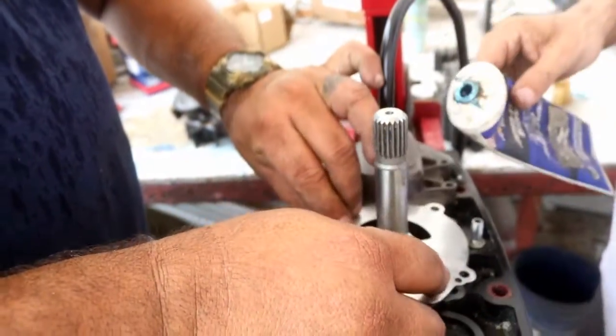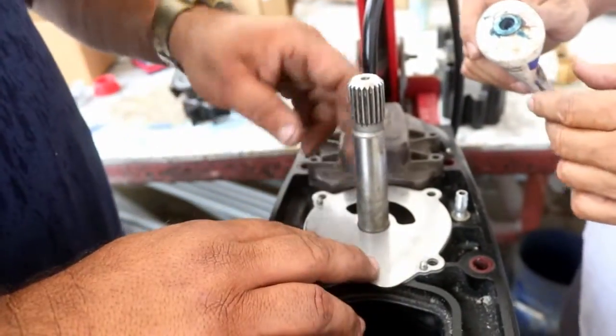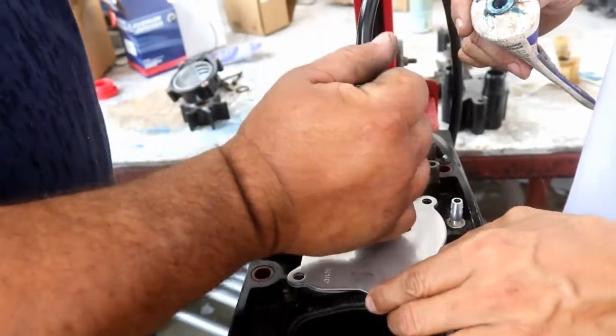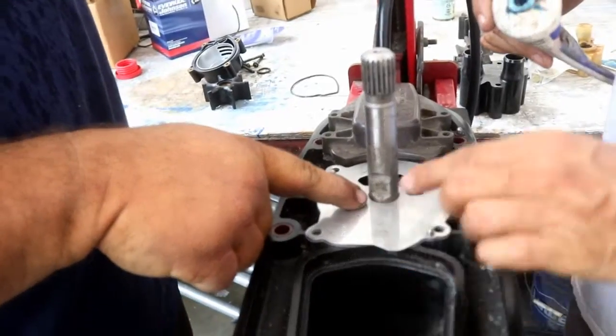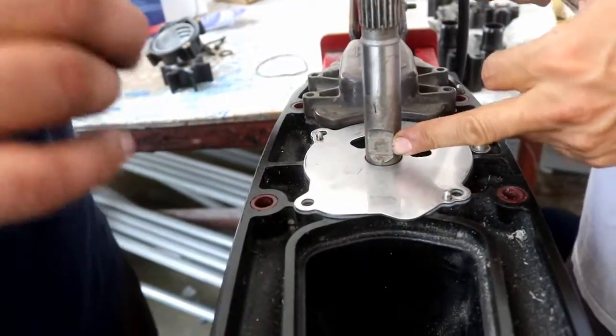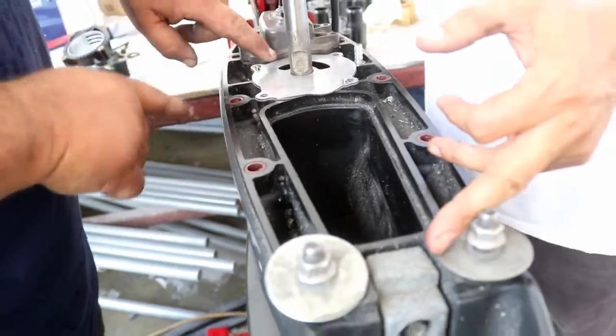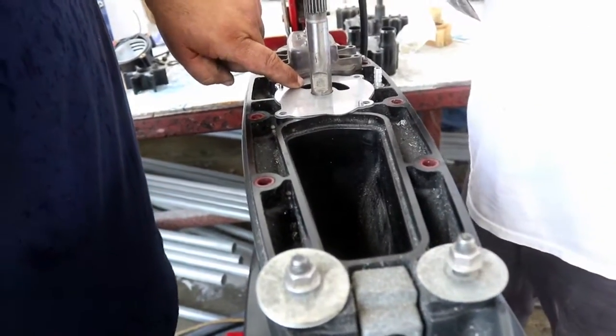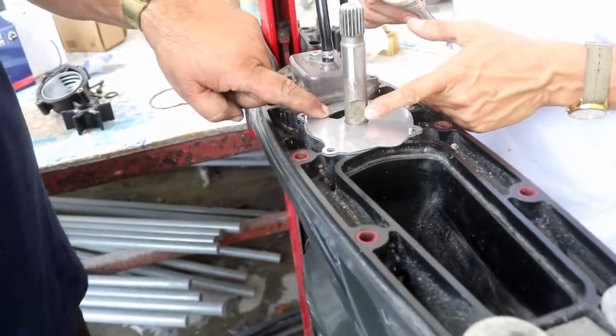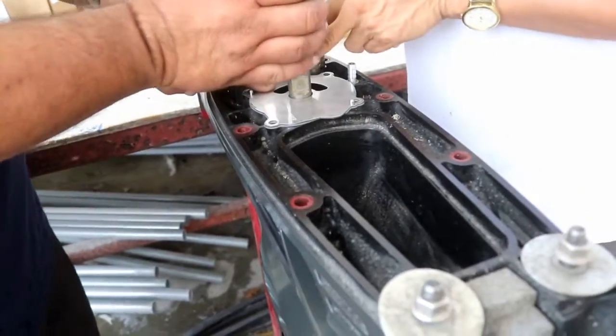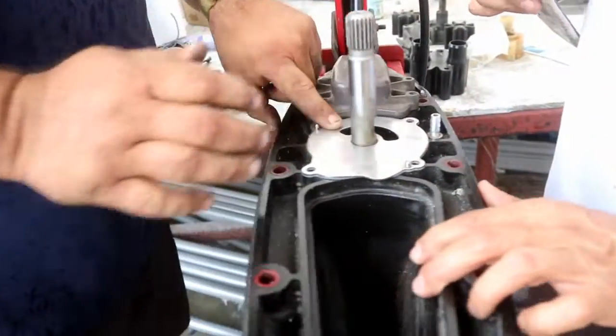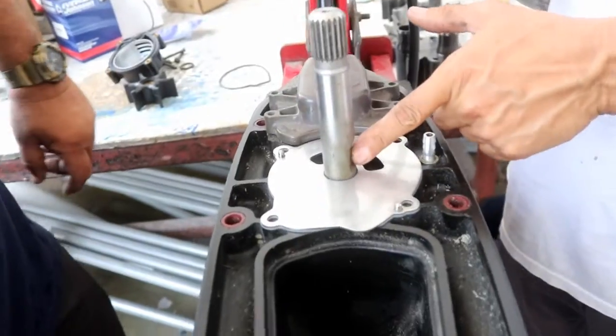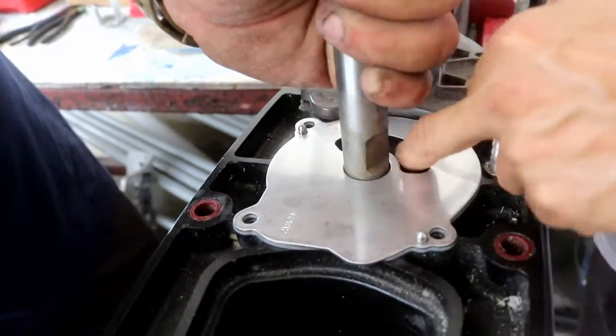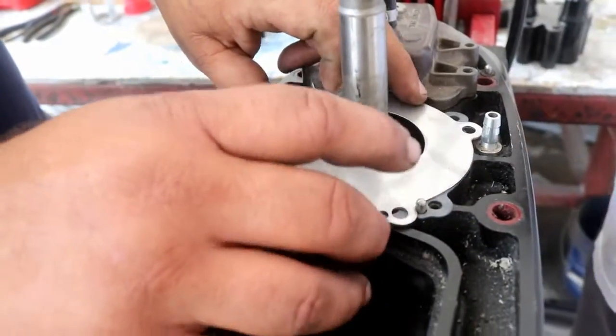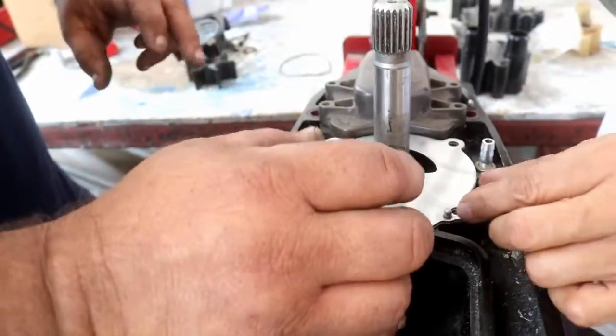If you need grease, we have grease over there. You put the wear plate, and what I normally try to do is have the keyway pointing this way. The reason I do that is so if you drop the key, it doesn't accidentally fall in - facing forward in order to avoid dropping the key in there, and you don't see it so it can go unnoticed. Right, if you have the key over there it can go into the hole, and that's not good - then you'd have to take everything back apart.